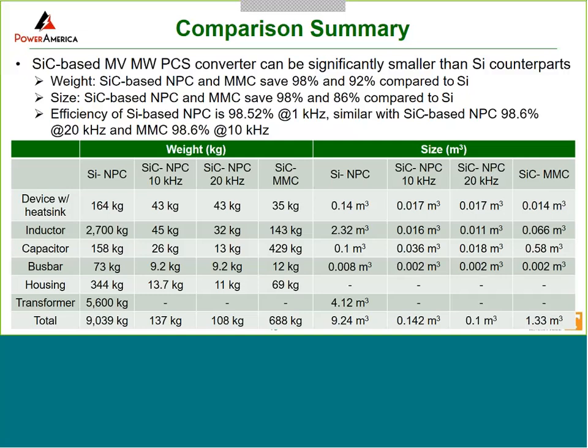The next question is, compared with a 3.3 kV system, the 10 kV system will have more clearance or creepage. How is it considered in the volume per unit of power density calculation? Right. Yeah, obviously that's a challenge. So when we do the higher voltage one, there have to be different requirements, which is not really different from the silicon system if we go to higher voltage. So in our case, we have considered them.